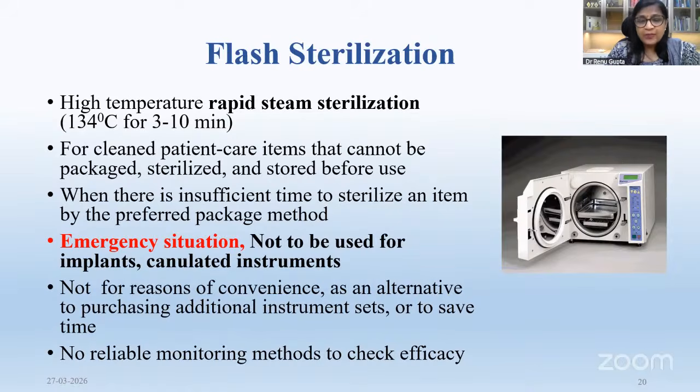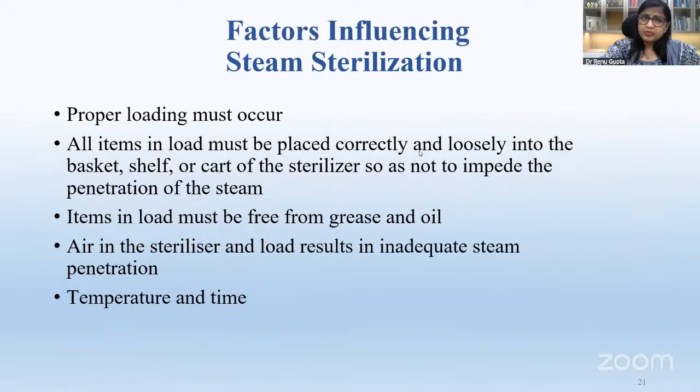This is just an emergency situation, not to be used for implants or your cannulated instruments, because the exposure is not very good. And please understand, flash sterilizer is not a reason for convenience. Just use it there only, because there is no monitoring method to check its efficacy. This is only an emergency sterilizer to be used only in rare circumstances, not as a routine. You get a short note on flash sterilization, so it is important again.